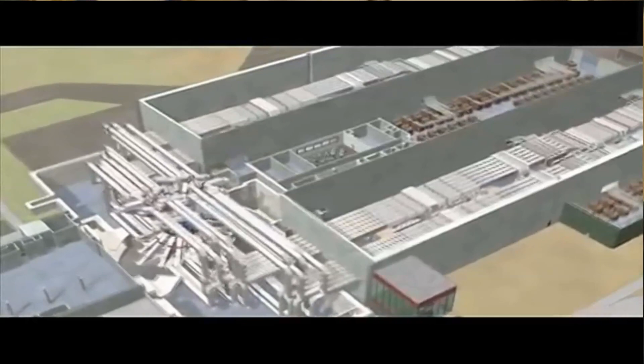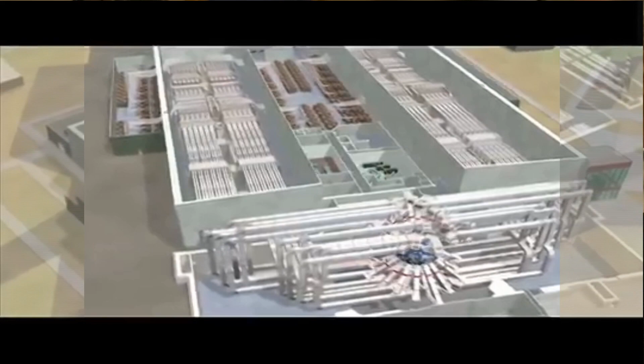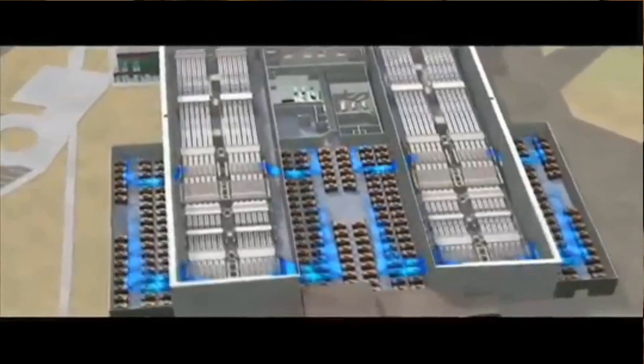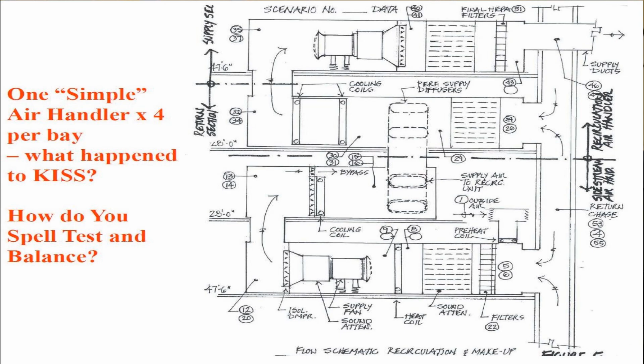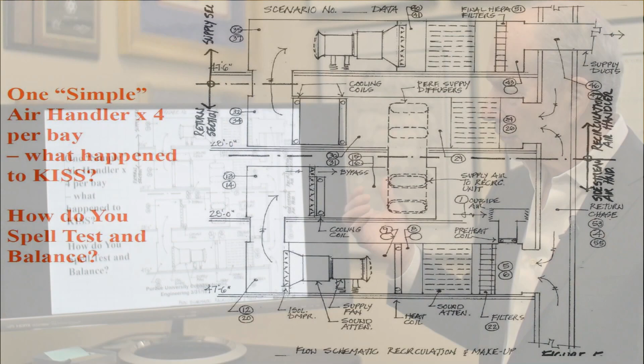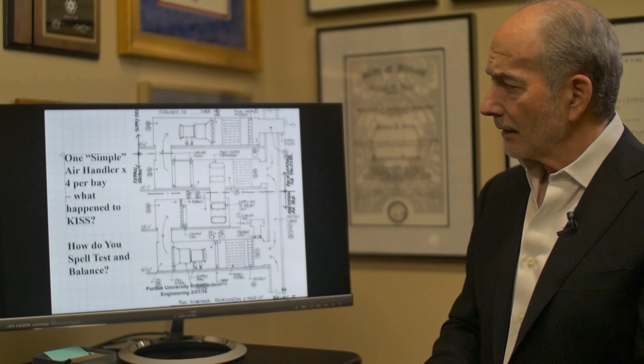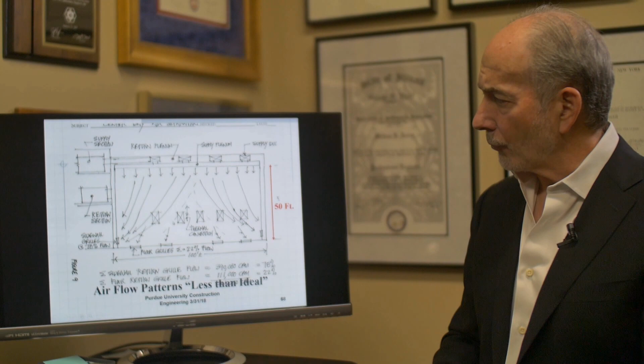So I was asked to evaluate, and here's a section through it. You can see the clean bays on either side of the capacitor banks. I was asked to analyze the air handling system and determine what could be done to improve the performance. Well, these were very complex air handling systems. In fact, what I had to do was take the drawings and kind of butterfly them, if you will. These air handlers were on 2 levels and not immediately obvious how they functioned together. Well, the truth is they didn't function together very well. So I evaluated the pressure hierarchies throughout the air handling units, the acoustical performance. We ran tests and determined that they could be simplified and allow the system to perform better.